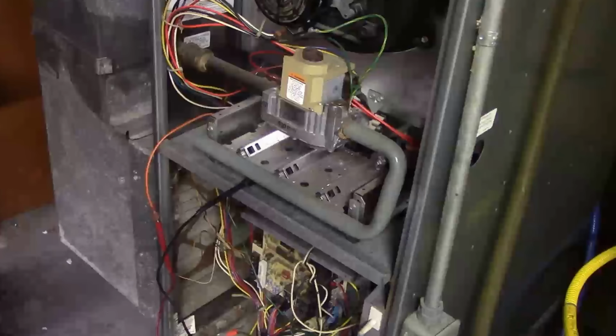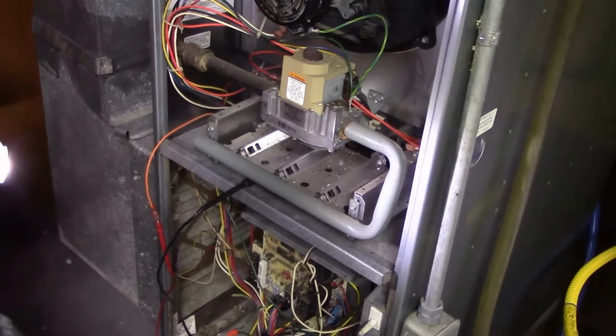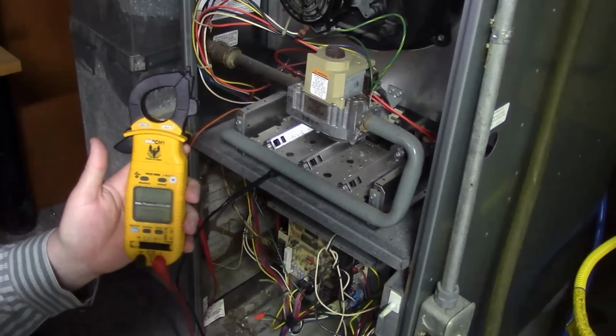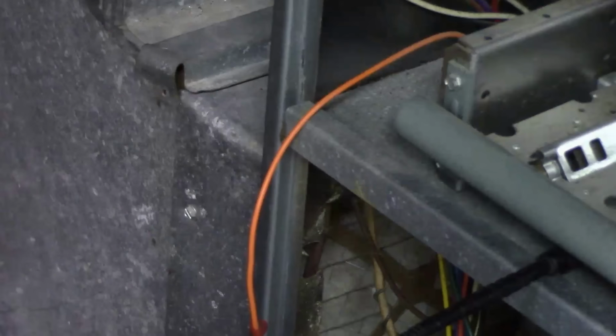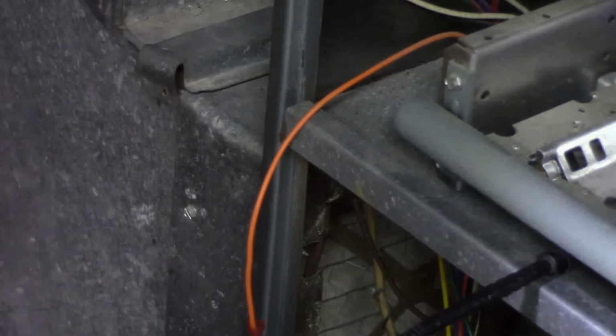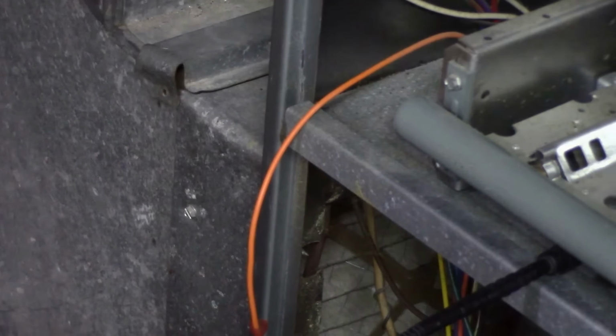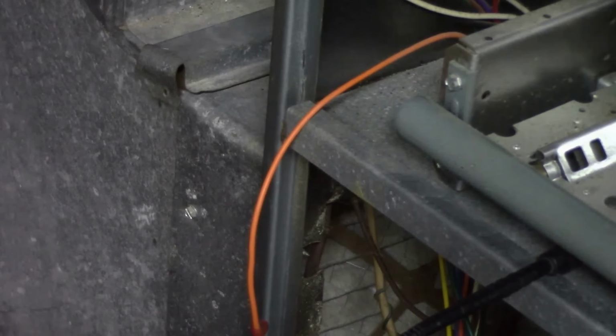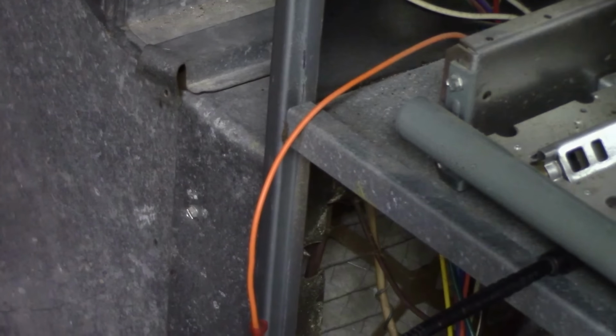The meter is set on what setting? That's right, microamps DC. When you look at it, like on mine, it'll say uA DC, microamps DC. We already have a call for heat on the thermostat, just like this. So we're going to fire it up. Just have to remember to hit the door switch. That's found on here. And if you're wondering where the door switch is, give me a minute and I will try to have that figured out for you.